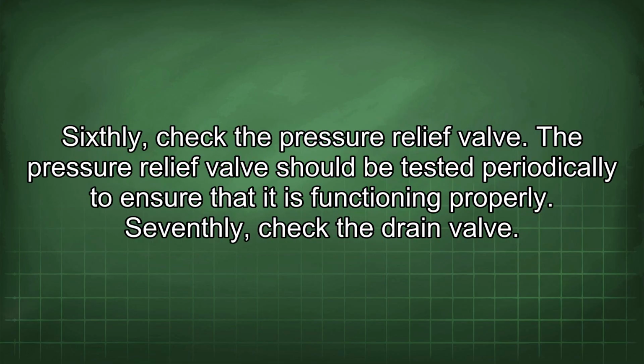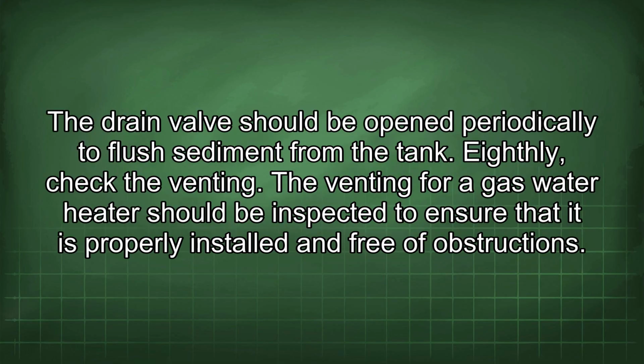Sixthly, check the pressure relief valve. The pressure relief valve should be tested periodically to ensure that it is functioning properly. Seventhly, check the drain valve. The drain valve should be opened periodically to flush sediment from the tank. Eighthly, check the venting. The venting for a gas water heater should be inspected to ensure that it is properly installed and free of obstructions.